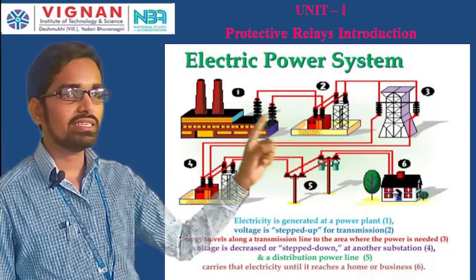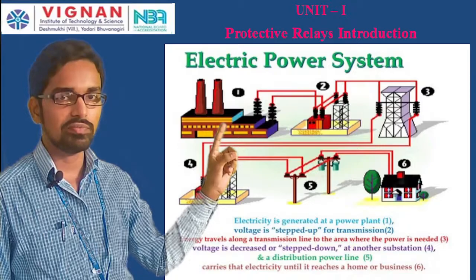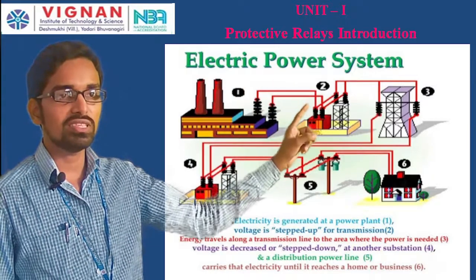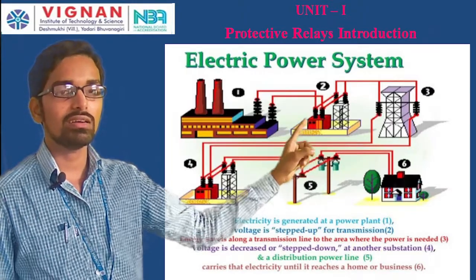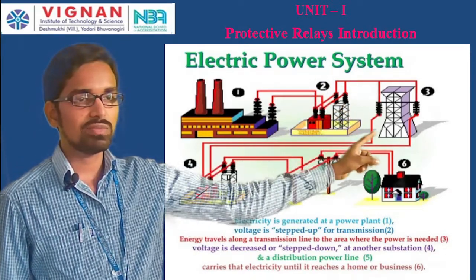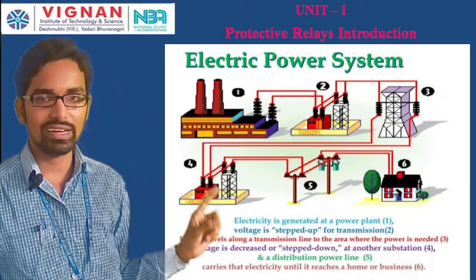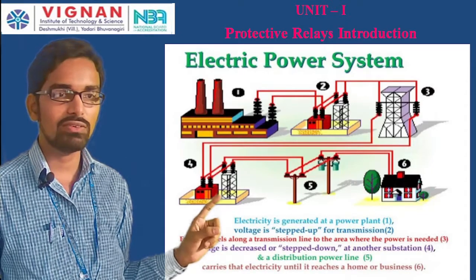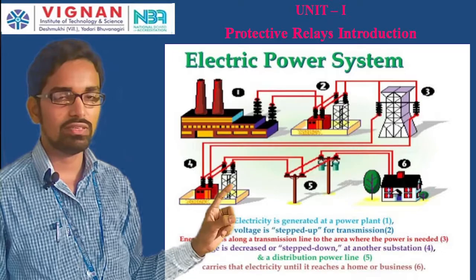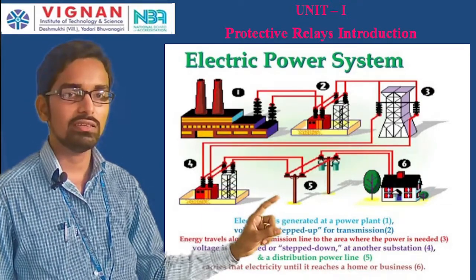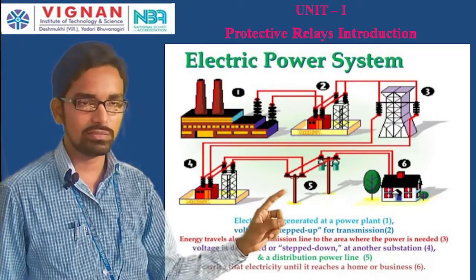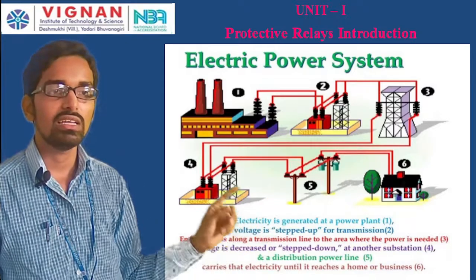In India, we mostly have 11 kV generation. That 11 kV is stepped up to 132 kV, 220 kV, 400 kV, or 765 kV for transmission. At distribution stations, 400 kV is stepped down to 11 kV for primary distribution, and then a further step-down transformer reduces it to 415 volts for secondary distribution.